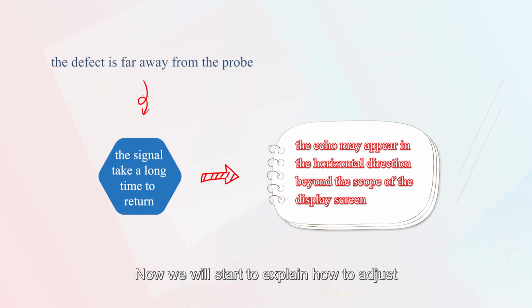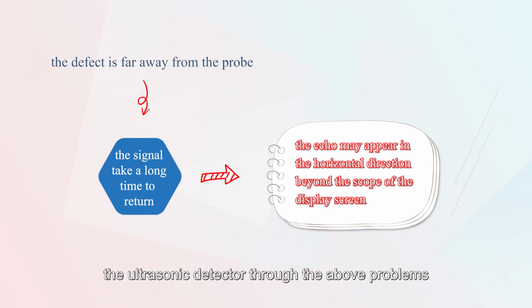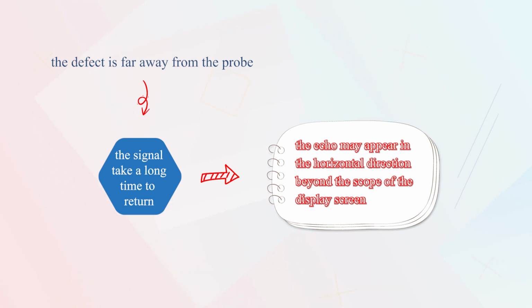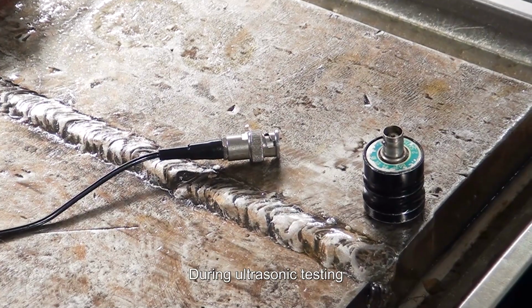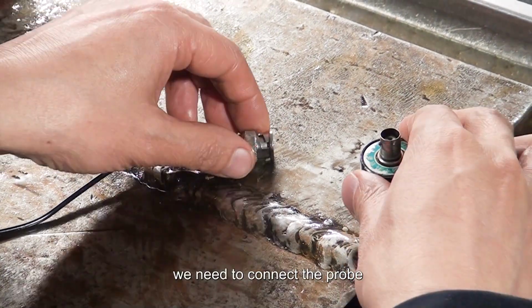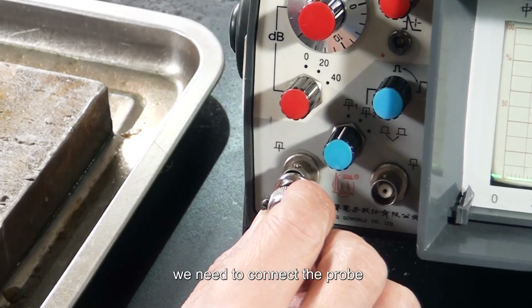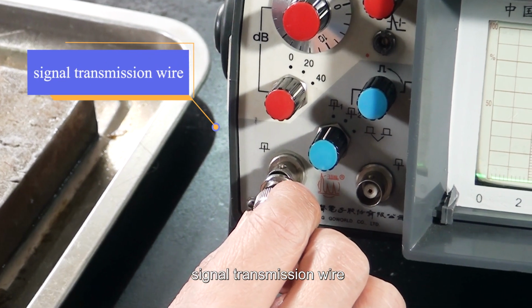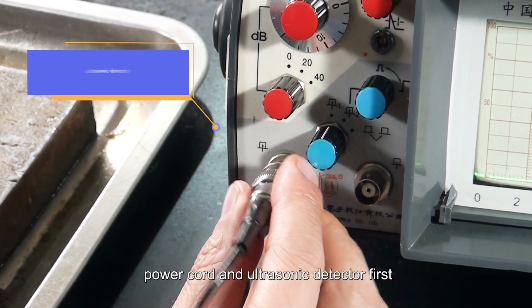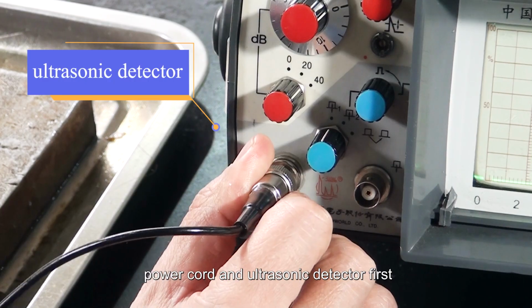Now we will start to explain how to adjust the ultrasonic detector through the above problems. During ultrasonic testing, we need to connect the probe, signal transmission wire, power cord, and ultrasonic detector first.